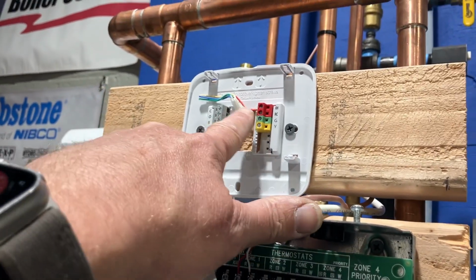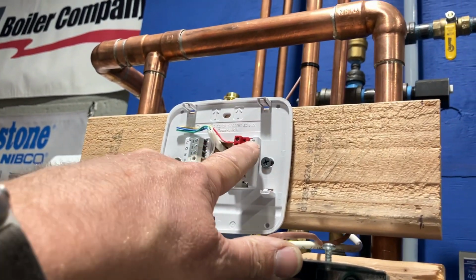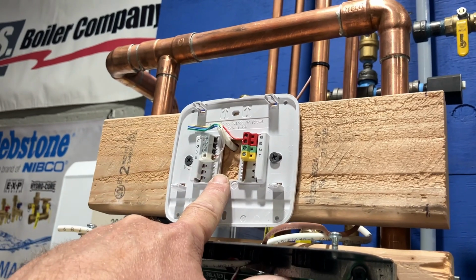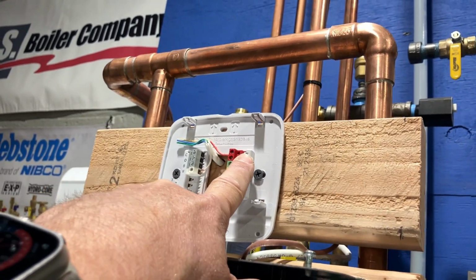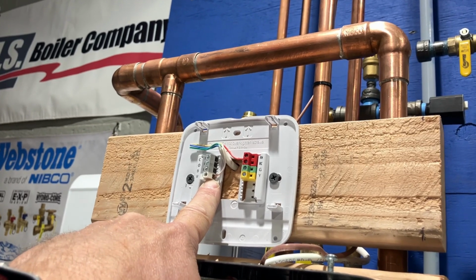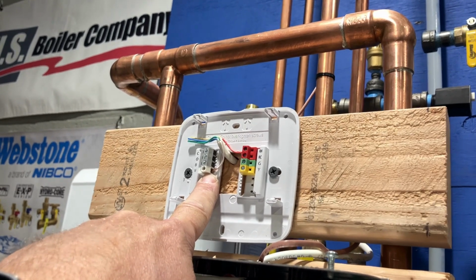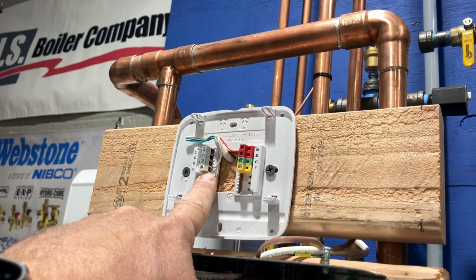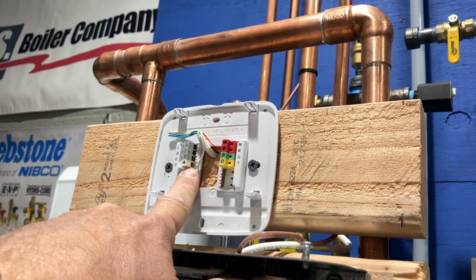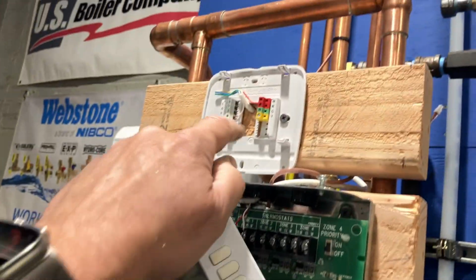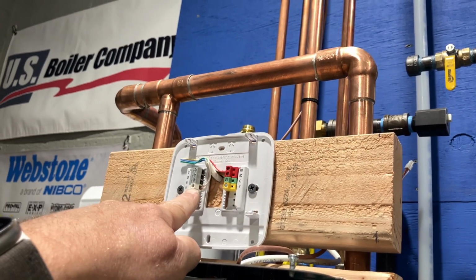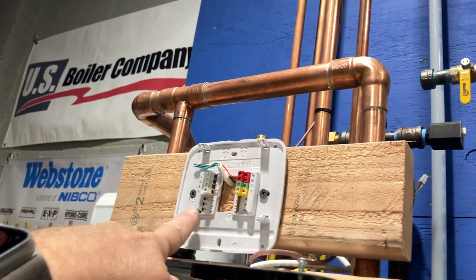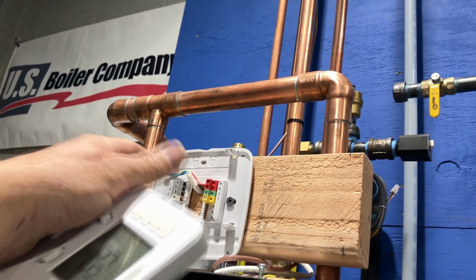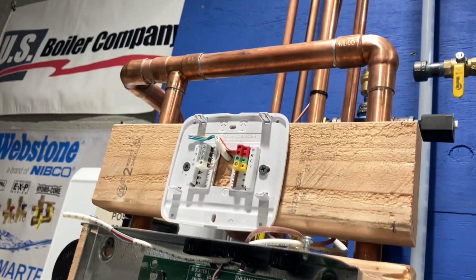All right, so we have a red wire, which is on RH. Now, this was a much simpler thermostat. You're just going to have two terminals, R and W. Standard heating only thermostat, like a little yo-yo, T87, Honeywell, for example. So when the thermostat is calling, the circuit between RH and W is closed. There's no power there, but the circuit is closed. Well, actually there's power, whatever, I'm not going to confuse anyone.